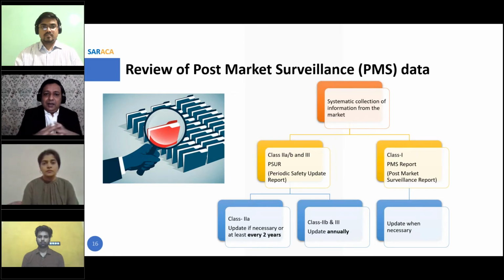If it is your own company, and your quality function gives you data on PMS, how do you really question that data to ensure that when you put up a summary of PMS in your CER, it is the best? So in the regulation, there is systematic collection of information from the market for class 2A, 2B, and 3. There is a PSUR requirement which needs to be completed every 2 years for class 2A. So you need to look at that PSUR. Class 2B and 3, it should be updated annually. So you need to look at the latest PSURs when you write CERs and ensure that they are written appropriately.